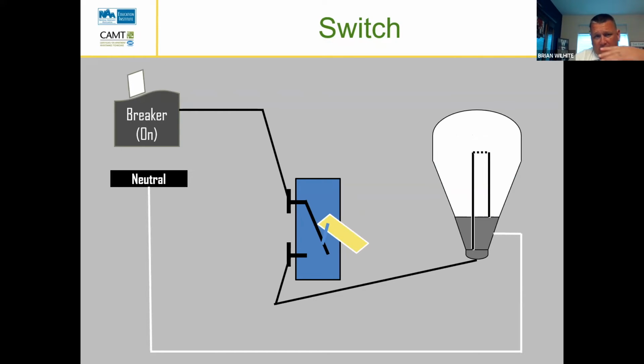But you can look here, we've got our breaker feeding 110 volt power to our switch. And that switch breaks the power from one side to the other to our light. And then from our light, we have a neutral coming back to our panel. So as this sits right here, right now, if I were to put my leads on my two terminals on my switch, how many volts would I get? 0. 120. 120. Yeah, because there is a difference.